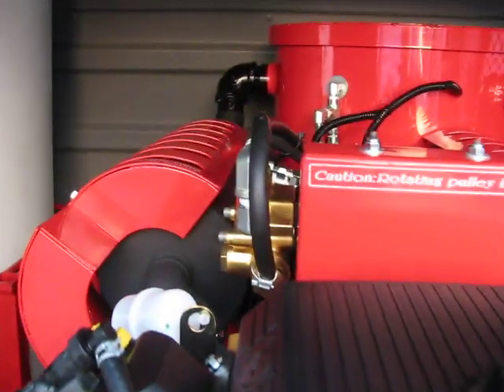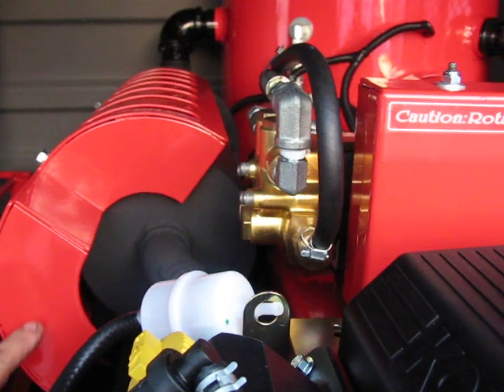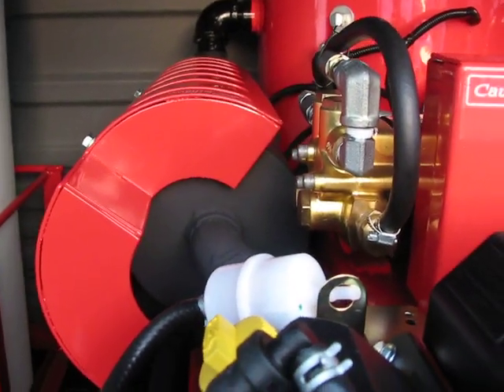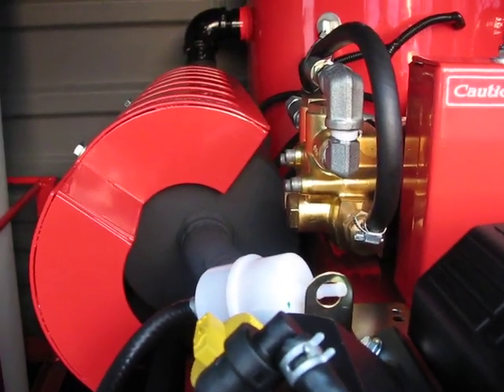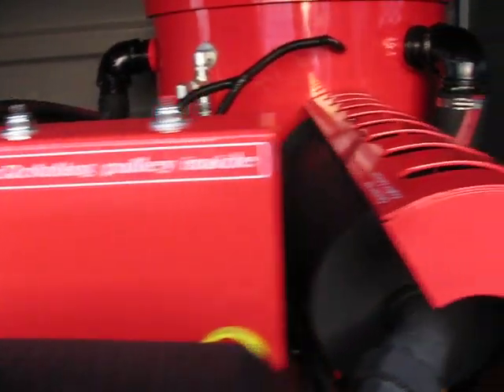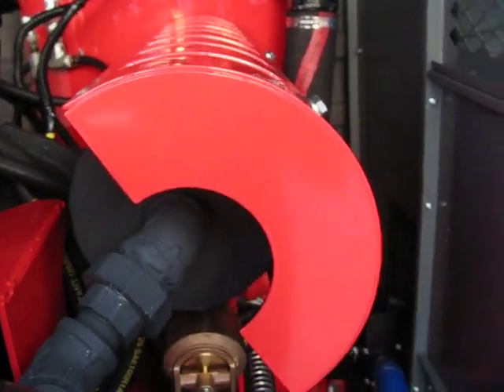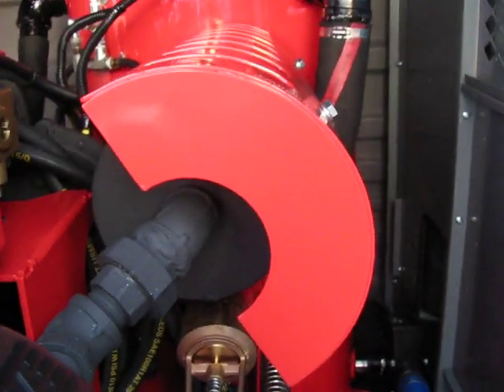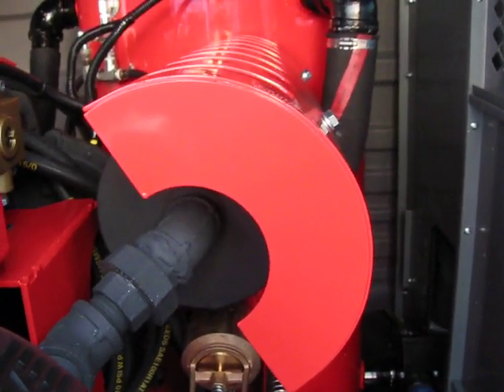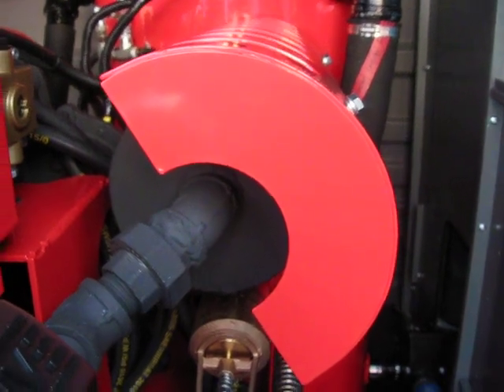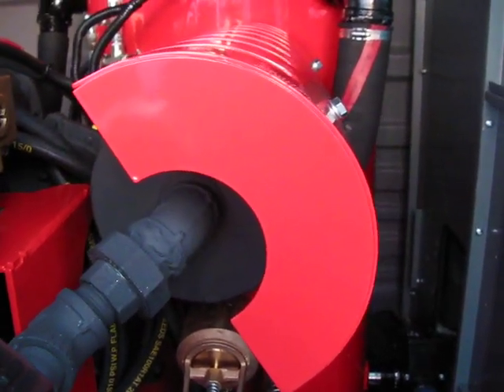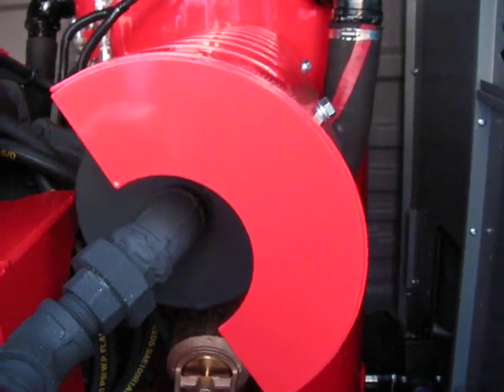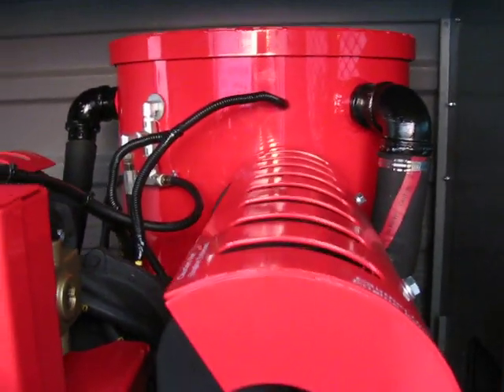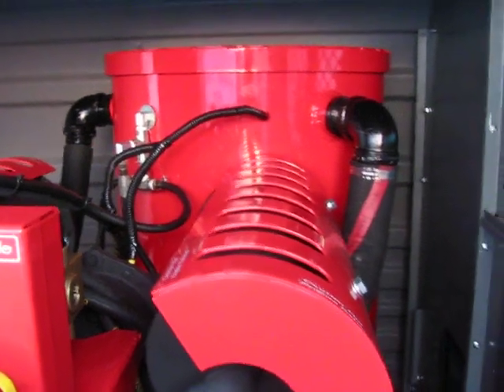Now, on the top, you have two heat exchangers in this system. You do have your preheater, which produces about 160 degrees of water temperature, and from there water moves to the right, which is your production line, which has no limit on temperature. You can set whatever you want on the thermostat inside of your temperature gauge. It will produce hot water up to that point, and if you're not using it, it will dump the rest into the recovery tank. Now if you notice on the top, it's your pressure pump, High Pro 2000 psi.